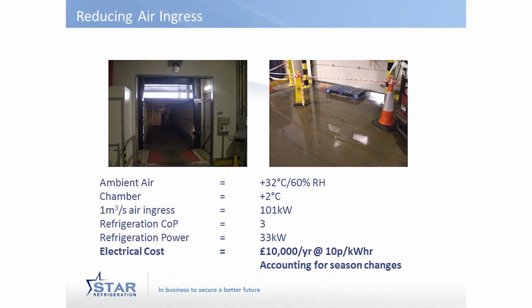The moisture is invisible, so nobody really pays any attention to it, but it's actually at least 50% of the additional load in the plant. In this case, on this side, the door was broken. They didn't want it to close fully because they couldn't get it open again, so instead of repairing the door, they stuck a pallet underneath, leaving a gap along the bottom.